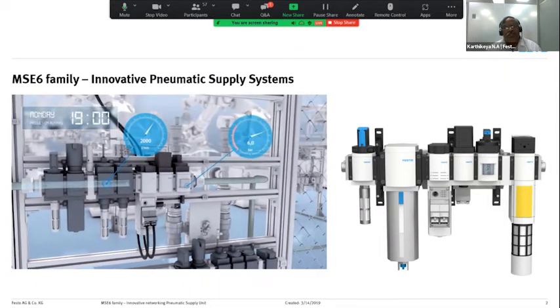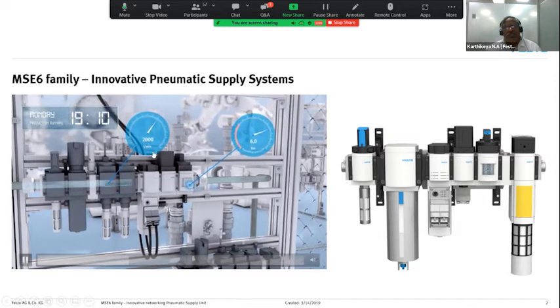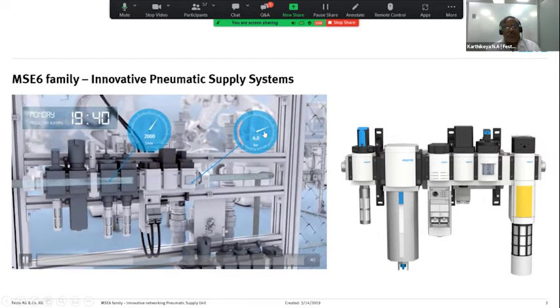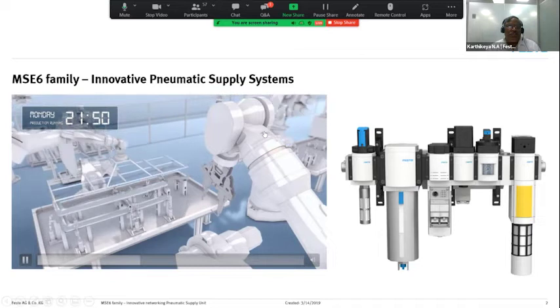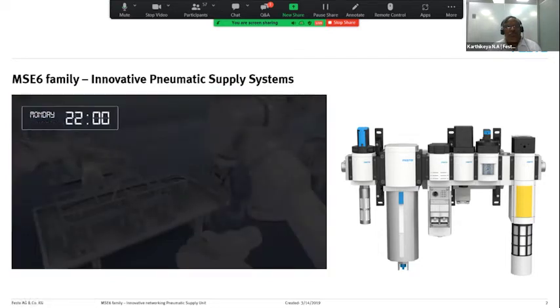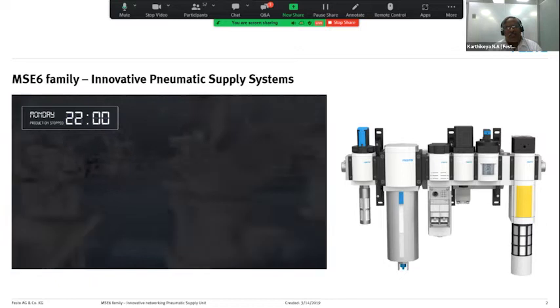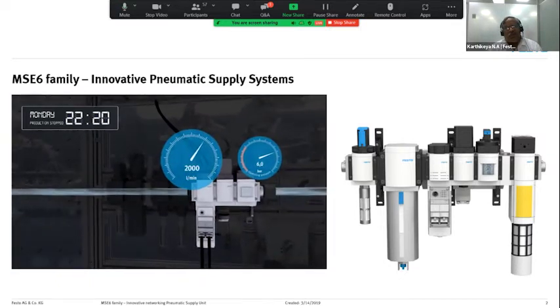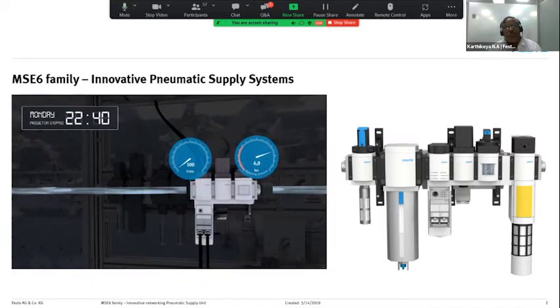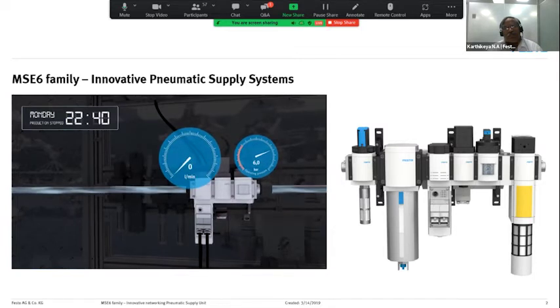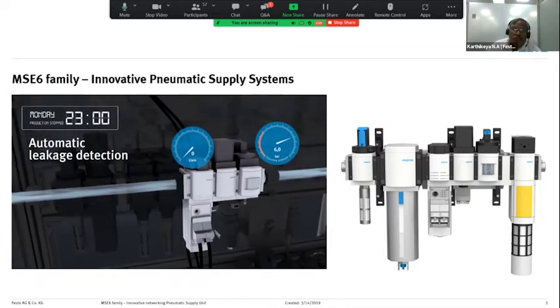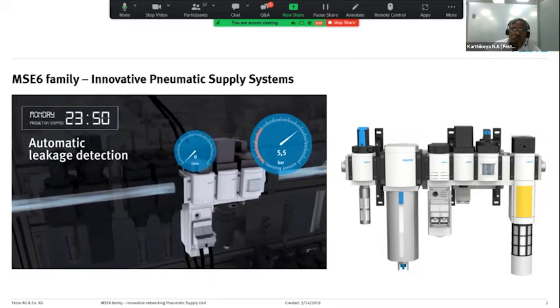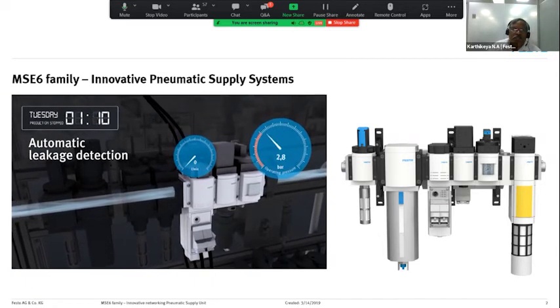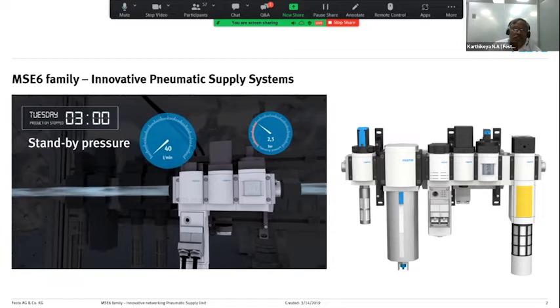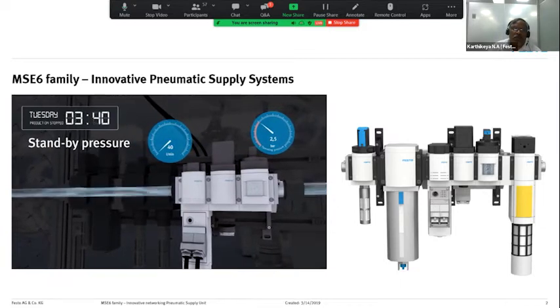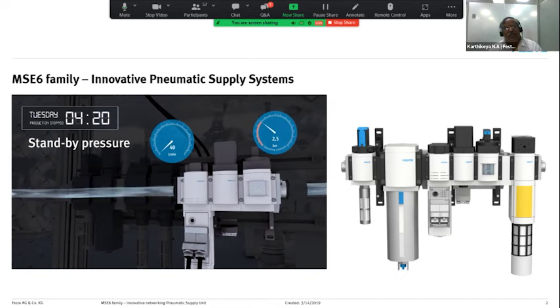When the production starts, you have a higher flow rate and you are monitoring the pressure level also. As it gradually increases and you are about to switch off or stop the process, your flow will reduce, and we are also monitoring the flow. You can also define when the flow comes to a minimum level. Normally, your flow should be zero whenever you stop your operations. But if there are leakages, then you have flow continuously happening. It will be detected by the flow sensor and automatically it will shut off. And this helps you in air saving.